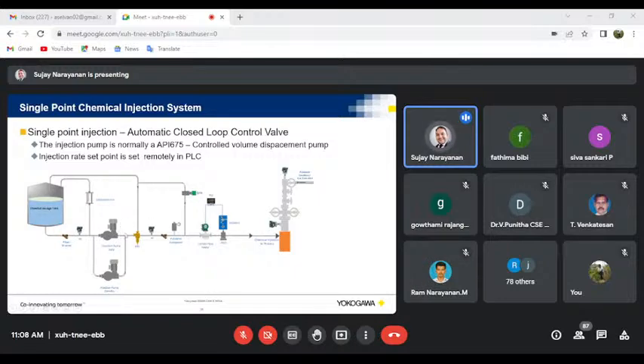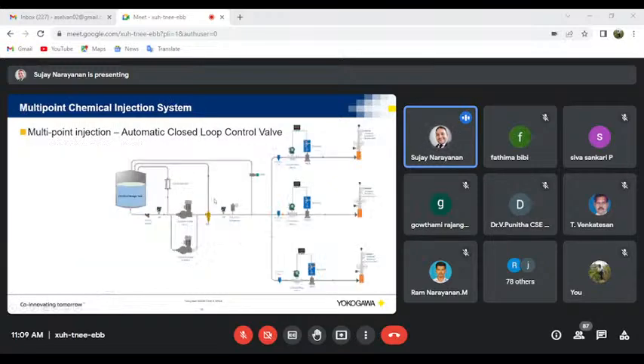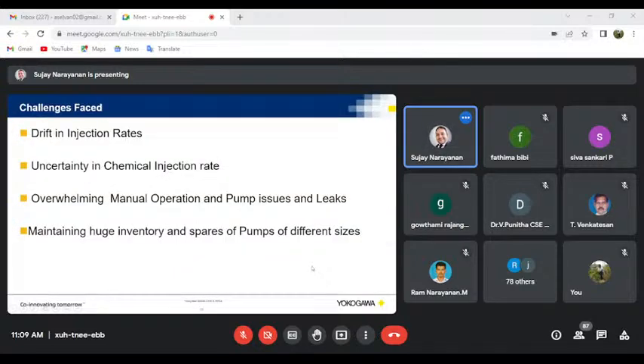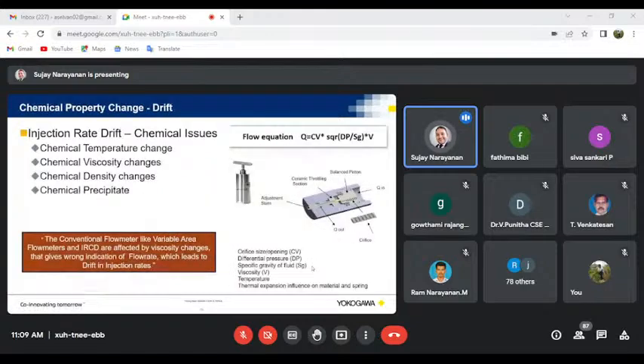That is the maximum discharge of the pump. Here we will try to control the flow rate using a flow meter, control valve, actuator and a PLC. Same thing if you are having a multi-point injection, you'll have a Coriolis flow meter or any flow meter, but mostly we use Coriolis for this application, and IRCDs for each line. I told you the challenges we have faced.